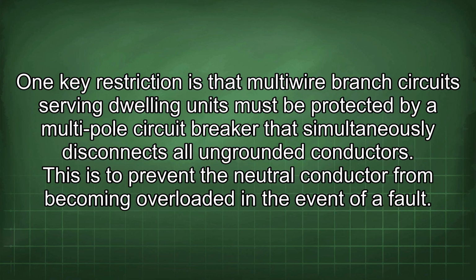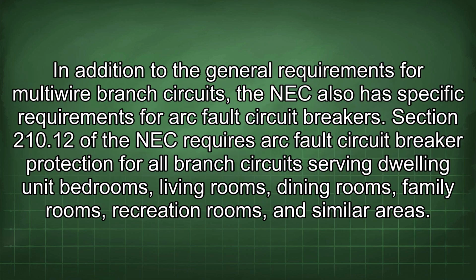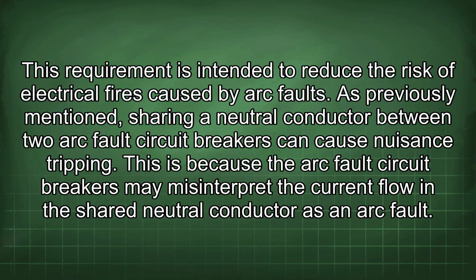One key restriction is that multi-wire branch circuits serving dwelling units must be protected by a multi-pole circuit breaker that simultaneously disconnects all ungrounded conductors. This is to prevent the neutral conductor from becoming overloaded in the event of a fault. In addition to the general requirements for multi-wire branch circuits, the NEC also has specific requirements for arc fault circuit breakers. Section 210.12 of the NEC requires arc fault circuit breaker protection for all branch circuits serving dwelling unit bedrooms, living rooms, dining rooms, family rooms, recreation rooms, and similar areas. This requirement is intended to reduce the risk of electrical fires caused by arc faults.